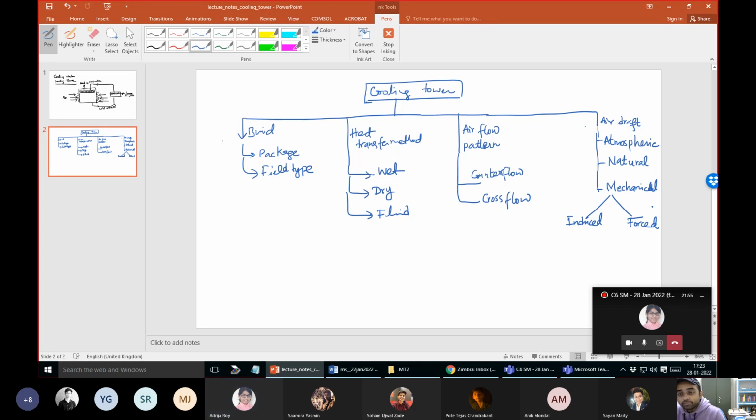No, do not get confused. In the shell and tube exchangers, you cannot cool the cooling water. Whatever cooling water we use in the shell and tube exchanger has to come from some other source. In heat exchangers, the operations we do are normally restricted to ambient temperatures, otherwise we have to use refrigeration. The cooling water temperature is normally 30 or 35 degrees in the Indian context. If you use that cooling water in the heat exchanger, the temperature will not drop below 40 degrees. So now the question is how to get this cooling water.